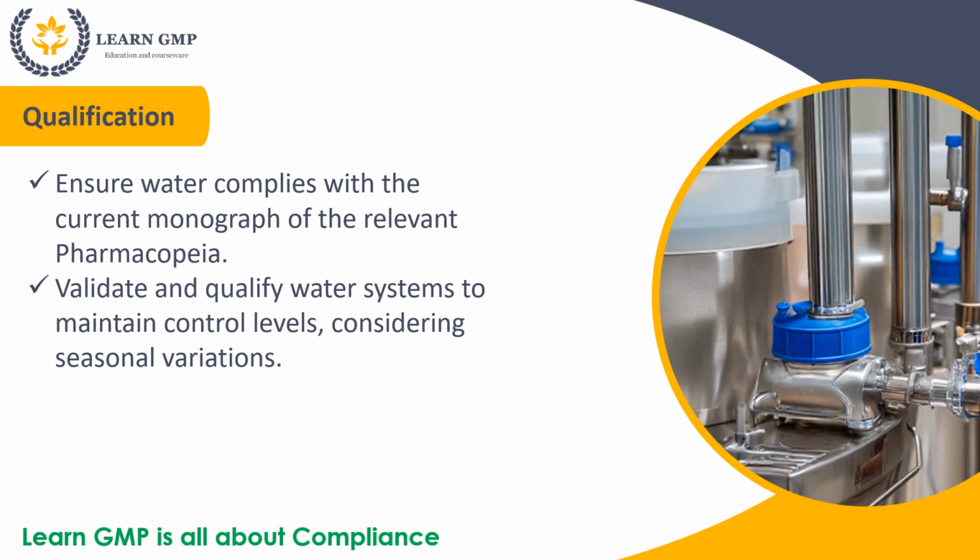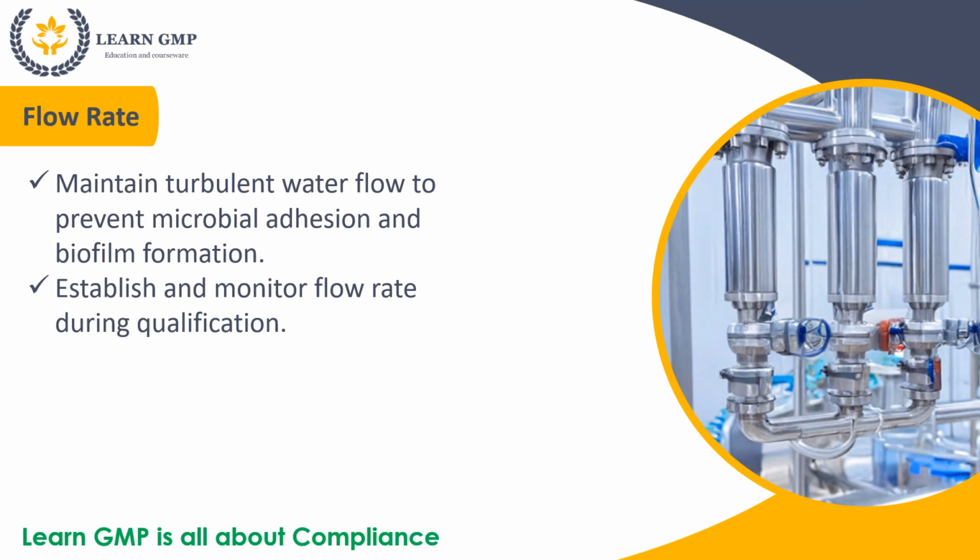Qualification. Ensure water complies with the current monograph of the relevant pharmacopoeia. Validate and qualify water systems to maintain control levels, considering seasonal variations. Flow rate. Maintain turbulent water flow to prevent microbial adhesion and biofilm formation. Establish and monitor flow rate during qualification.